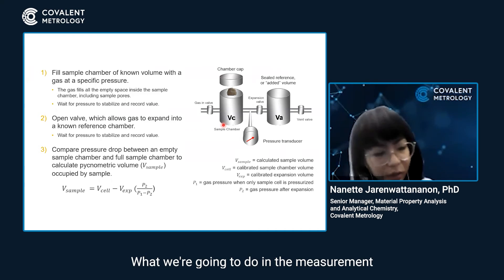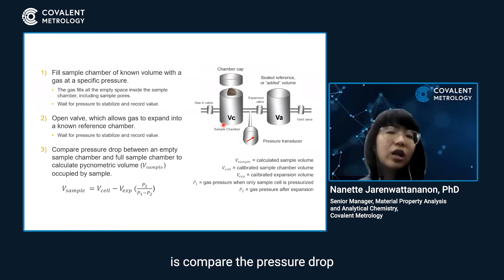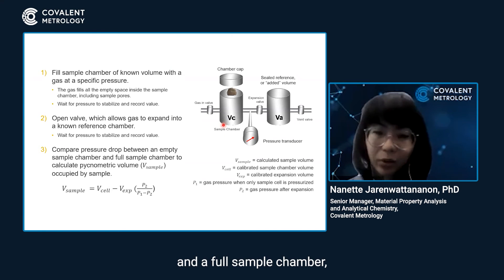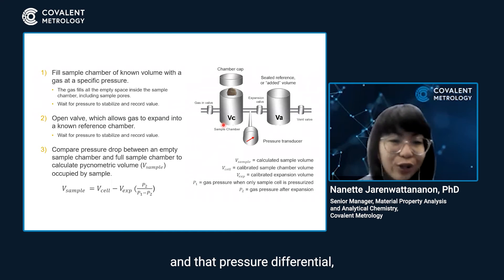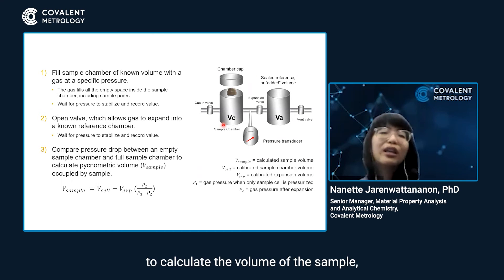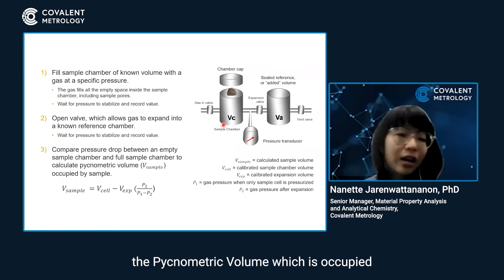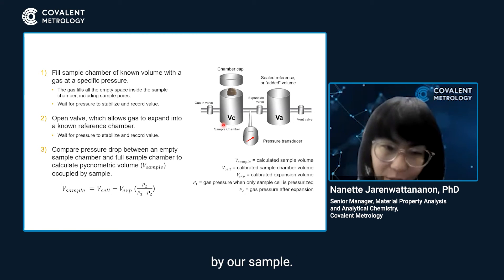What we do in the measurement is compare the pressure drop between an empty sample chamber and a full sample chamber. That pressure differential allows us to calculate the pycnometric volume occupied by our sample.